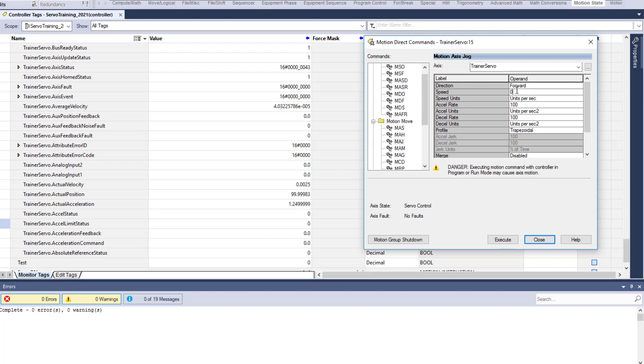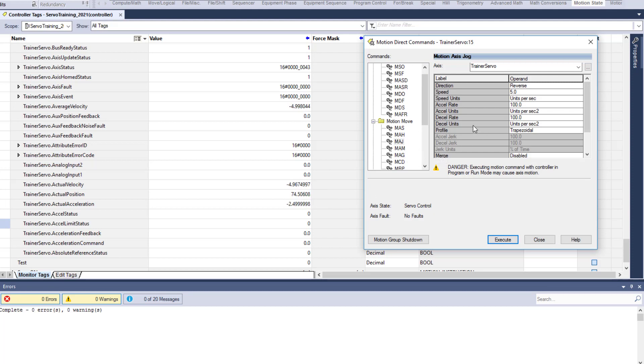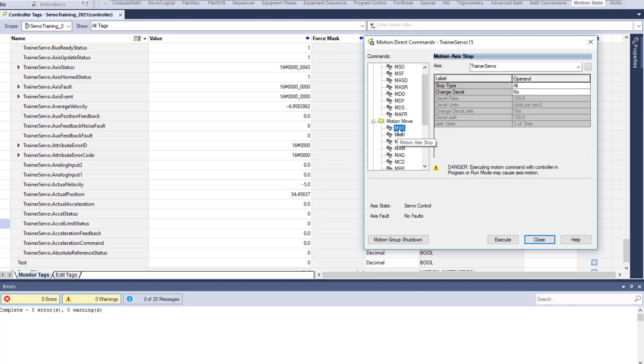The next way is again the jog — you can do forward or reverse. If you want to do a reverse, put in five for that matter. You can jog it in reverse — you can see it jogging. Now it's not going to stop in jog mode. To stop the servo, I need to come in and execute a MAS, which is a motion axis stop. You can see the drive is stopped now.